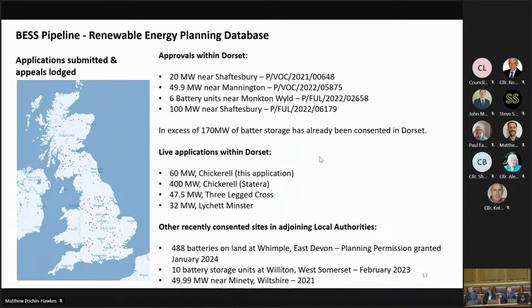Within Dorset, the council has granted planning permission for a number of BESSes, shown on screen here: a 20 megawatt facility near Shaftesbury, an almost 50 megawatt facility near Mannington, a 6 battery unit scheme at Monkton Wyld, and a 100 megawatt scheme near Shaftesbury. Together these total in excess of 170 megawatts of battery storage consented in Dorset.